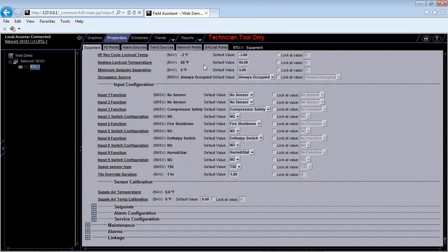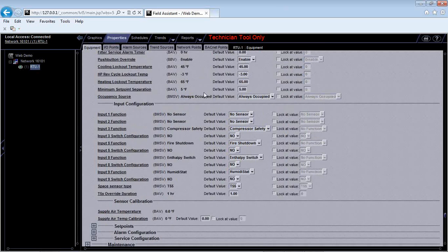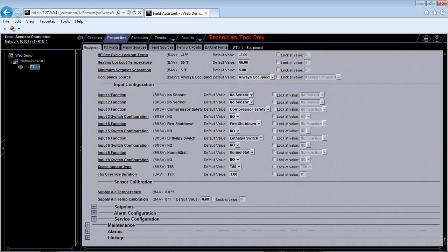That's adjustable. Your minimum set point separation. This is an important value here, okay? This 5 degrees is the delta between your heating and cooling set point, the minimum delta that you can have, okay? So, for instance, if I have a 70 degree occupied heating set point, the lowest occupied cooling set point I can go to is 75 degrees because I have this 5 degree minimum set point separation, okay? So if I want to bring that heating and cooling set point a little bit closer, I first have to adjust this value to, let's say, 2 or 3 degrees before I can actually make the change on my set point. If I change it on my set point locally, it will not adjust that value.